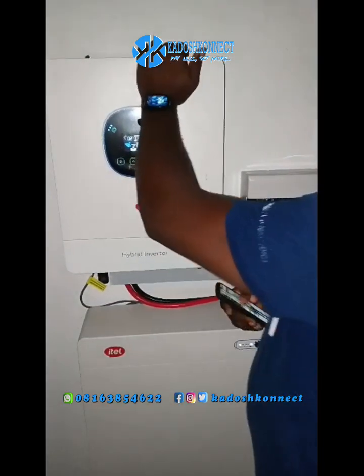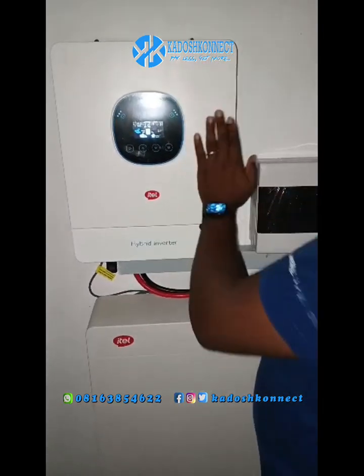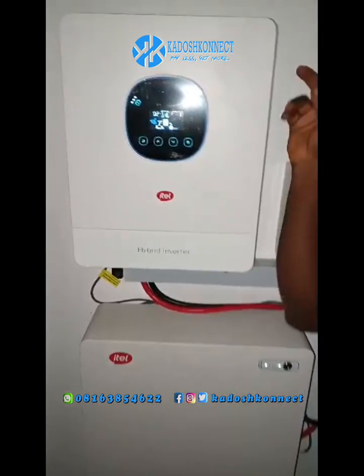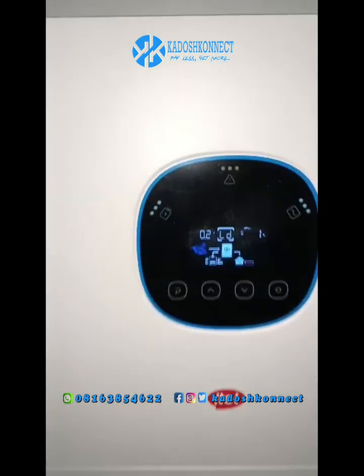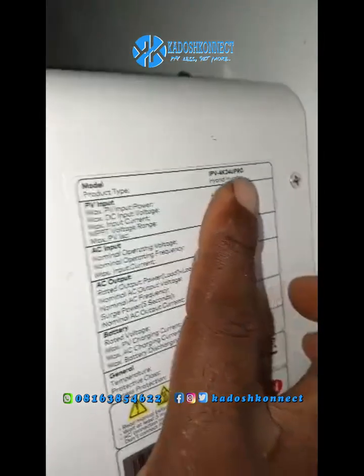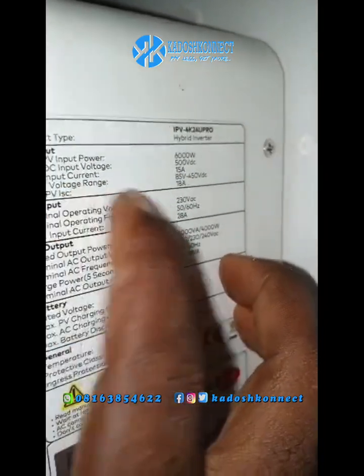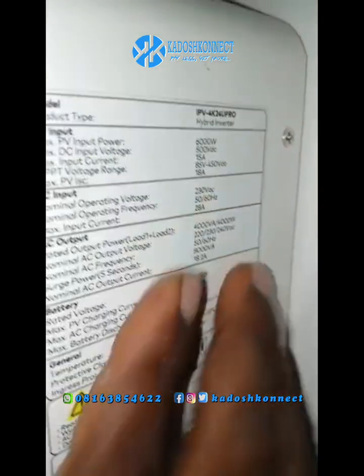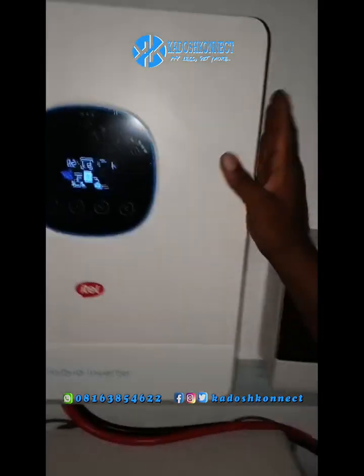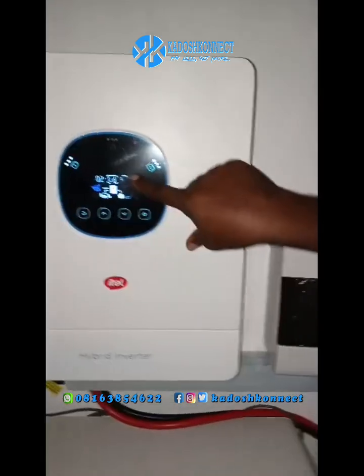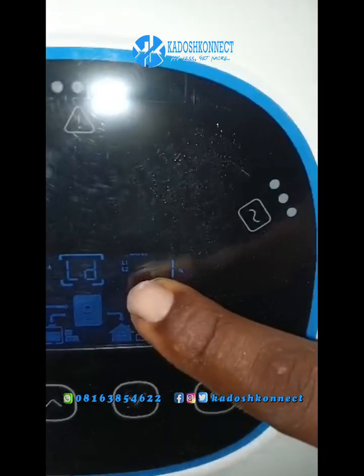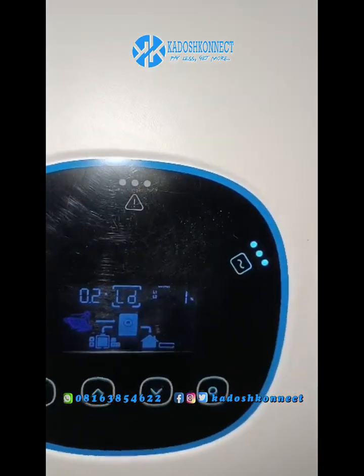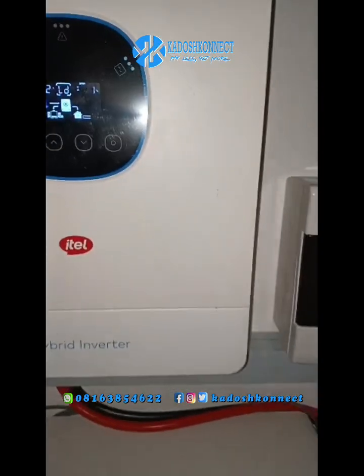This is a 4 kW hybrid inverter. The hybrid inverter has the capacity of 6,000 watts PV. You can see it here. So the PV input is 6,000 watts and the voltage input for PV is 500 volt DC. So the maximum voltage you can take from panel is 500 volts. But it has only one MPPT tracker. But it has two outputs, L1 and L2. So it has a normal load and the smart load. L2 is always smart load.